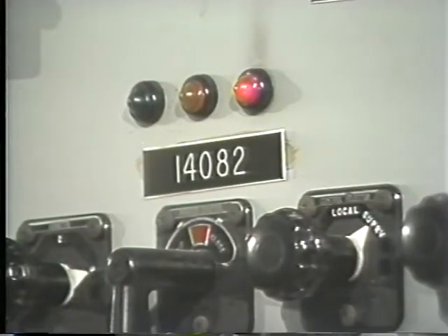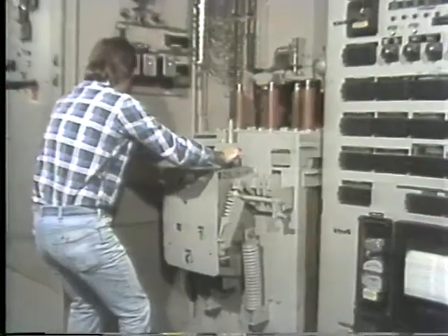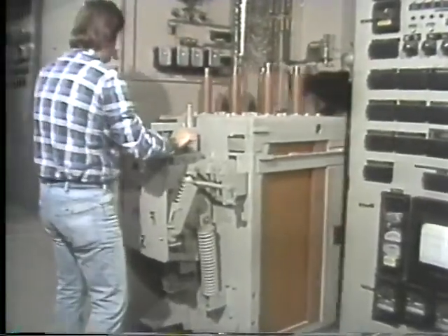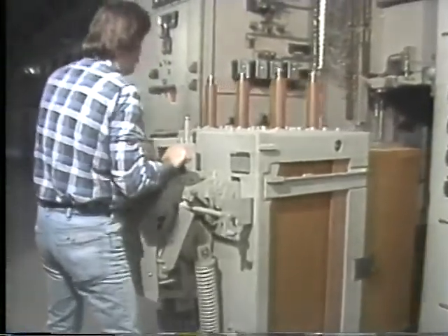We've seen one example, but many installations use other methods on 4 kV and 14 kV equipment. A common technique is to ground a line, a transformer, or a bus with a ground test device that racks into a breaker panel. First, the line's unloaded and de-energized, typically by the dispatcher. The next step is to rack out the breaker so it's no longer in the circuit and roll it out of the way.